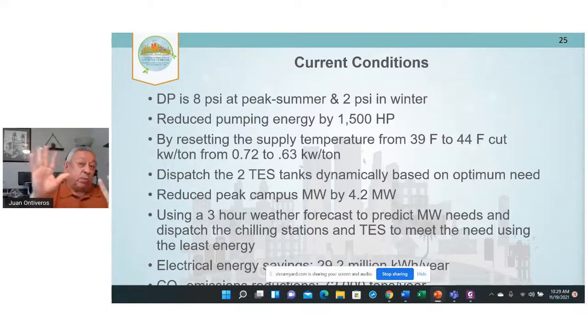To give you a perspective, I used to see delta Ps of 70 psi. So it's a bunch of horsepower. What ended up happening is we actually reduced our pumping energy by 1,500 horsepower. And by resetting the temperature from 39 to 44, we cut our kW per ton from 0.72 to 0.63. Immediately, we could see that.